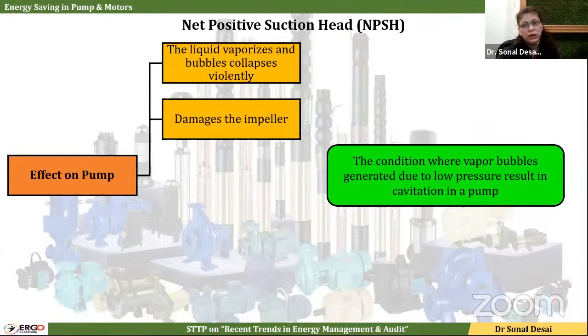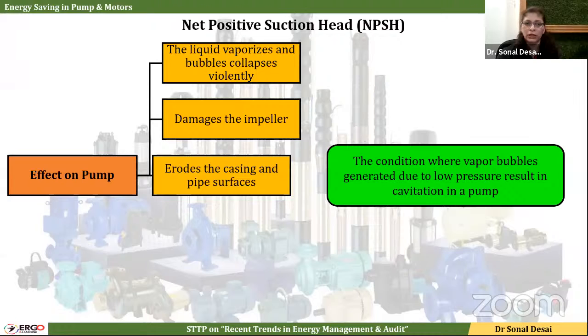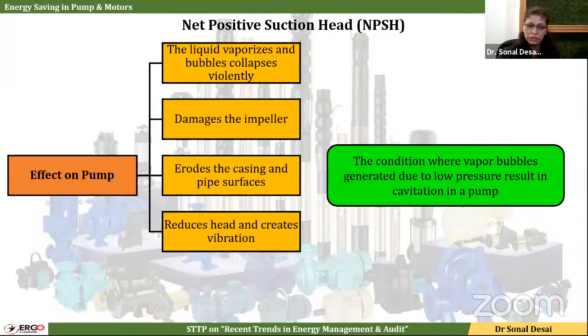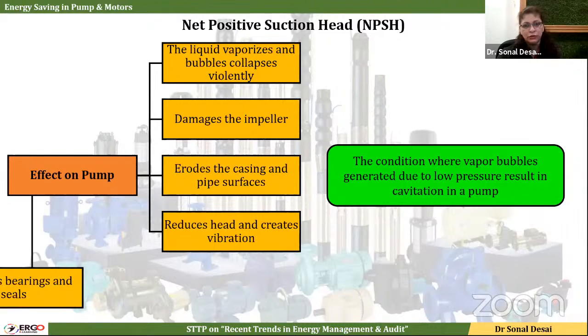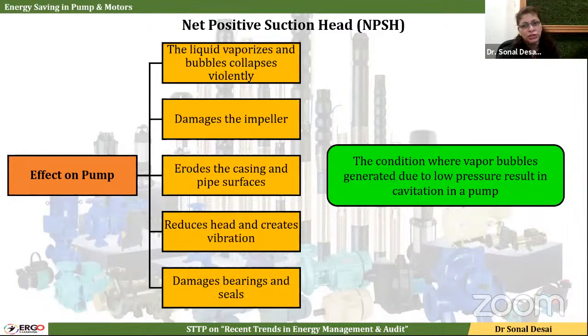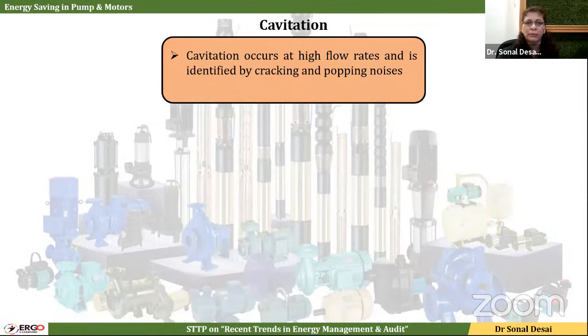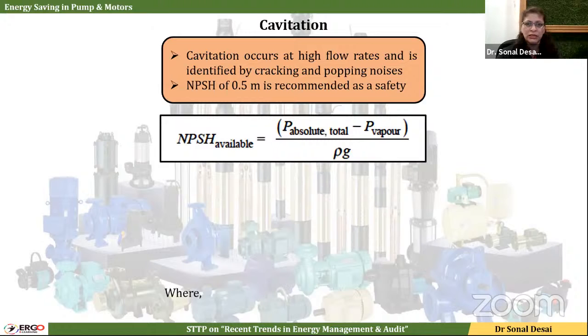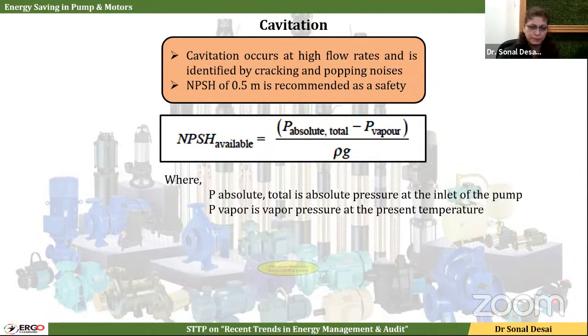This vapor bubble will create a blanket of vapor that will damage the impeller. It will create undue noise, erosion, damage to pipe surfaces, and vibration as well. By and large, it will damage pump working. It will damage the bearing, and we have to change the bearing frequently. This may happen if the required pressure is not maintained. So this cavitation can be avoided if we maintain NPSH, and it is recommended that plus 0.5 meter of NPSH is always maintained compared to the required pressure.